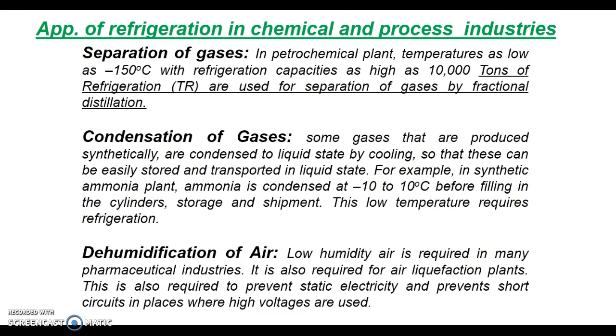Application of refrigeration in chemical and process industries: Separation of gases — in petrochemical plants, temperatures as low as minus 150 degree Celsius with refrigeration capacity as high as 10,000 tons of refrigeration are used for separation of gases by fractional distillation. Condensation of gases is another area in chemical industry where refrigeration is used. Ammonia plants are usually used with a temperature of condensation of around minus 10 to plus 10 degree Celsius. Dehumidification of air required for various applications is also produced using refrigeration processes.